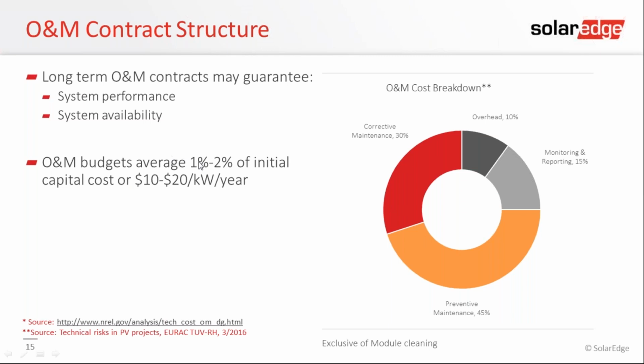O&M budgets on average are about 1 to 2% of your initial capital costs. So what I like to say is it's about $10 to $20 per kilowatt per year. So if I had a 200 kilowatt system, that would be $2,000 on the low end per year, and if I'm warranting that for 10 years, that'd be $20,000. Hopefully that math made sense.